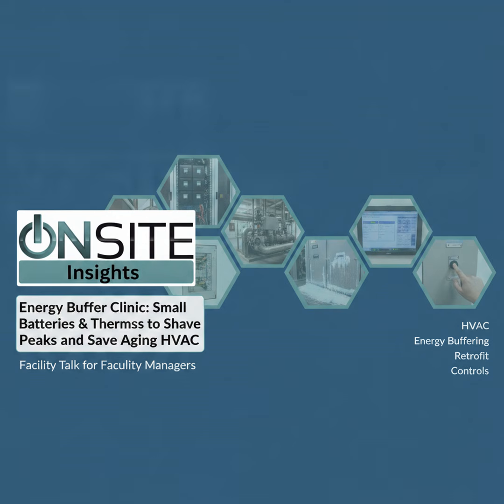For control-side UPSs, confirm the unit's listing and failure mode. Does it fail safe? And add the changes to your O&M documents. You mentioned micro examples earlier. Can we get a quick cost and sizing sketch so a manager can justify a pilot?